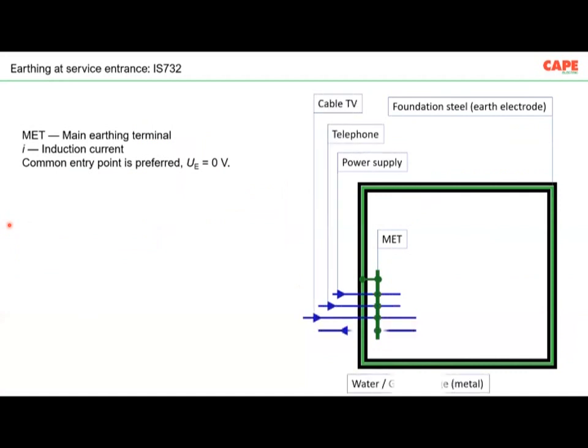Every building, at the service entrance, that means at the main switchboard, for whatever metallic services are coming from outside, we are supposed to create an equipotential bonding. In the picture, what I am showing is a metal water pipe, gas and sewage pipe, telecommunication, power supply, and so on. This actually has three purposes. The first purpose is protective equipotential bonding. During a fault, people inside the building shall not get a shock. Also, there shall not be any spark. So the first is no shock, no spark.